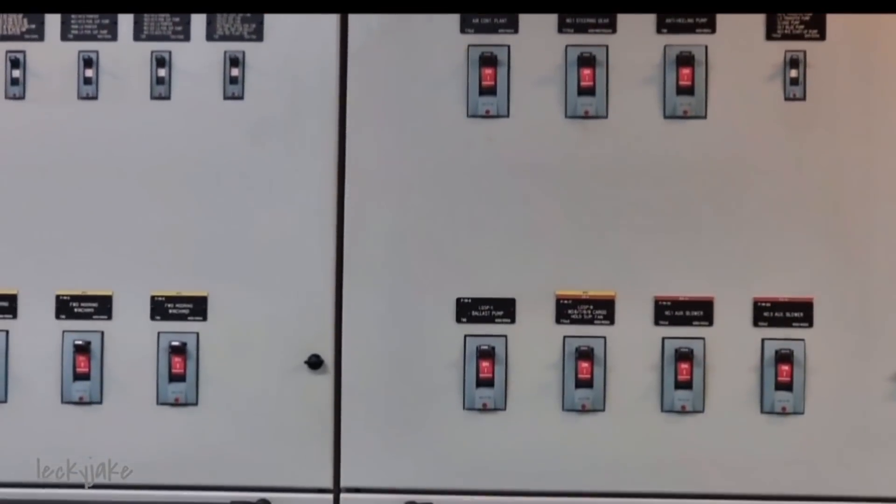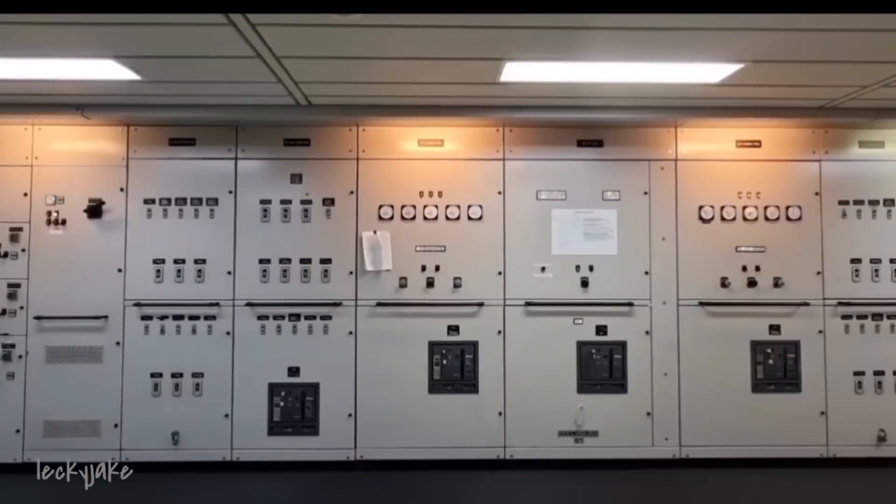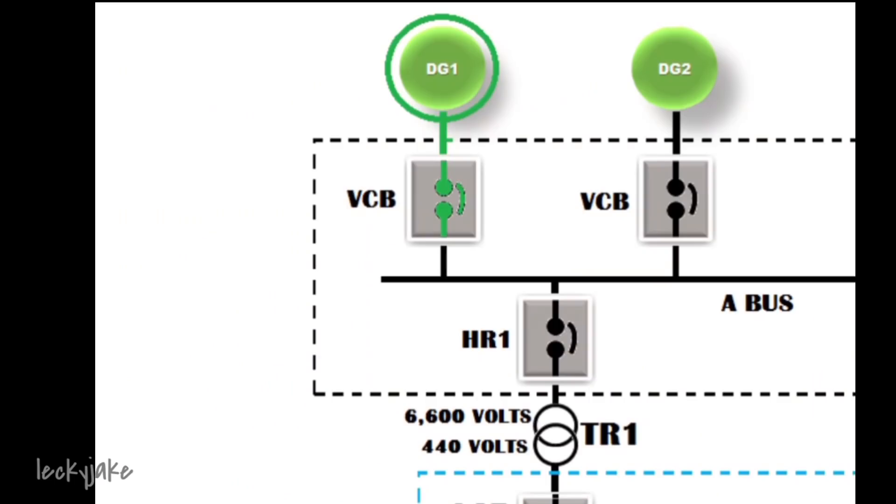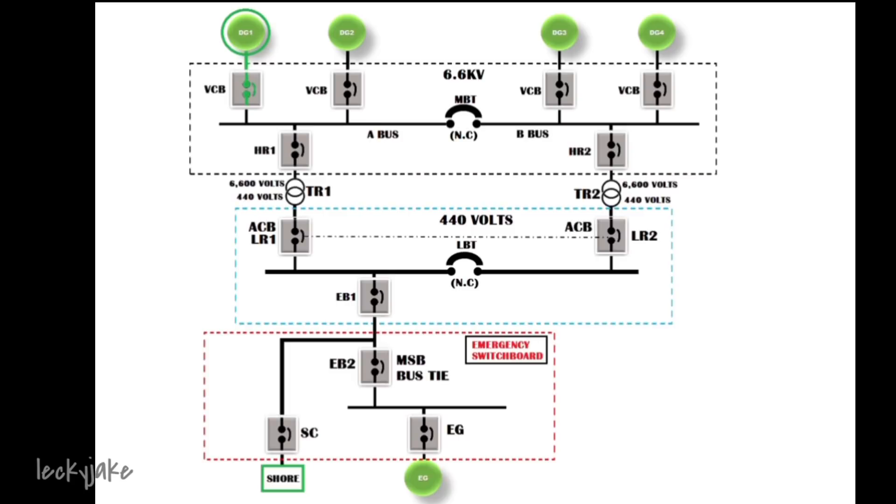So here's the more detailed explanation regarding the line diagram of our power management system. Let's say for example that the DG1 is the running generator. The VCB will be in closed position hence the DG1 will feed 6600 volts into the main switchboard. The main bus tie which is normally closed will also link the two bus bar, bus A and bus B. Hence in this setup, the whole bus bar has a 6600 volts supply. The number of running generator requires depends on the demand.